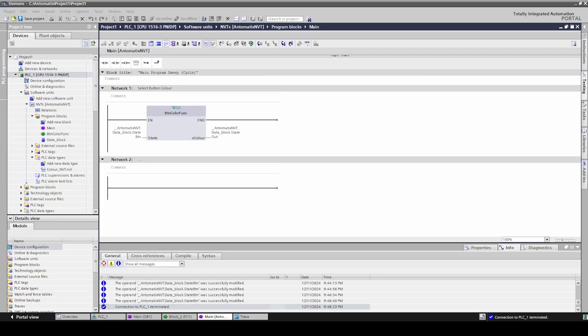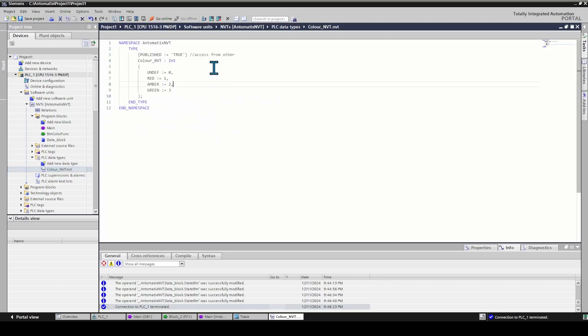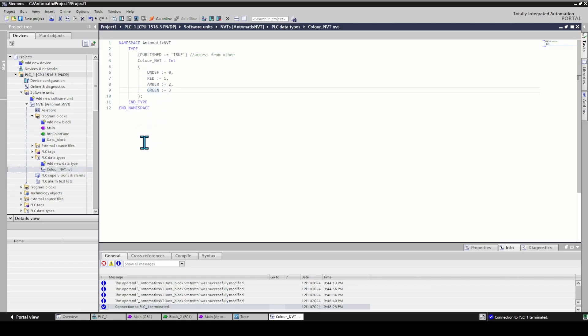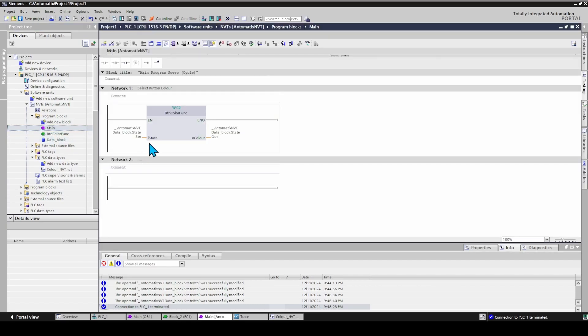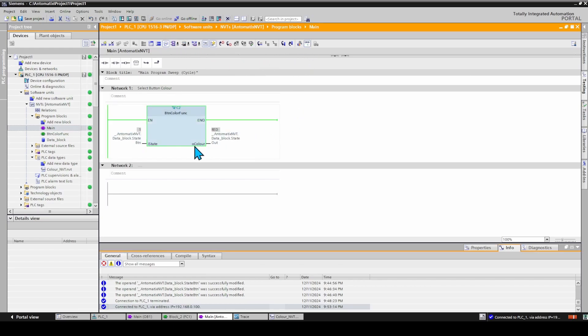Now let's see how this looks on a simple example. Here is an NVT for various colors assigned to an integer value. I'm going to open our block, which simply copies an integer into an NVT. We can go online now — we can see our value on input as 1 and the output displays the name of the color: red.